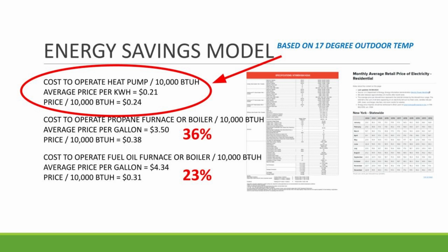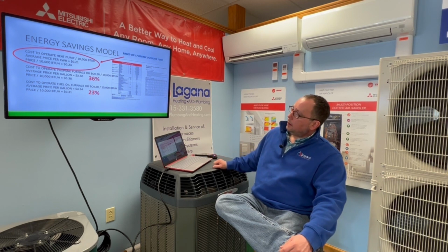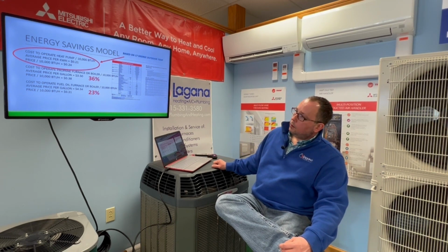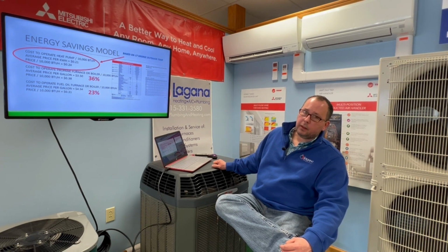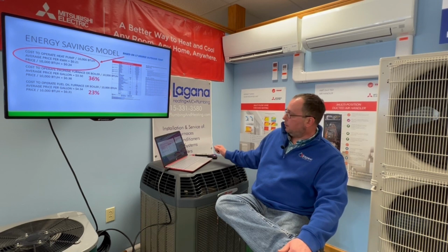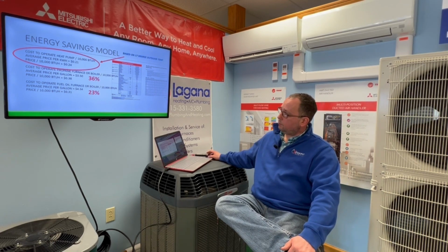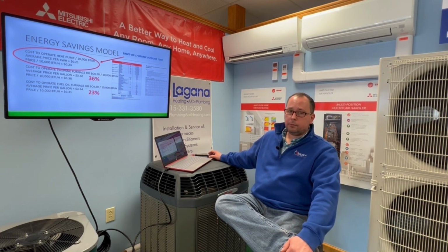And the interesting thing about this is, as the outdoor temp increases, so does the efficiency of my heat pump to a certain degree, and you will see it actually will cost less per 10,000 BTUs as the outdoor temp increases. That's not the case with a propane or oil furnace or boiler. They do not do that. So this actually, those will improve as the outdoor temp increases.